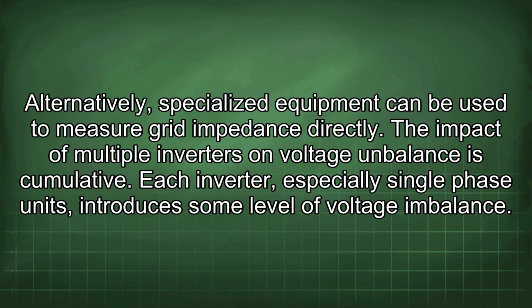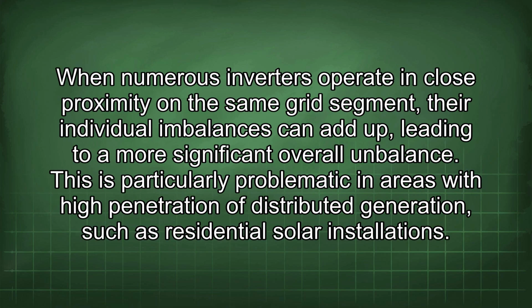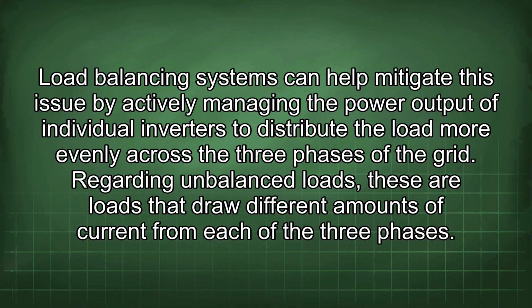The impact of multiple inverters on voltage imbalance is cumulative. Each inverter, especially single-phase units, introduces some level of voltage imbalance. When numerous inverters operate in close proximity on the same grid segment, their individual imbalances can add up, leading to a more significant overall imbalance. This is particularly problematic in areas with high penetration of distributed generation, such as residential solar installations. Load balancing systems can help mitigate this issue by actively managing the power output of individual inverters to distribute the load more evenly across the three phases of the grid.